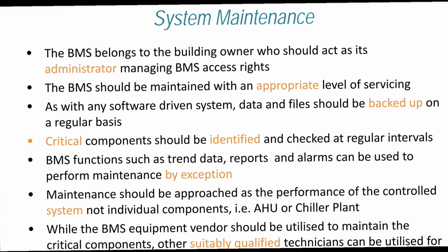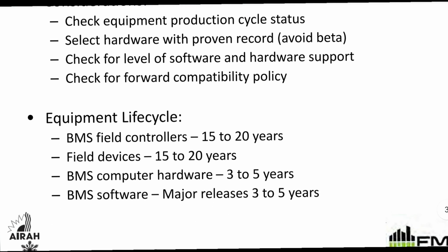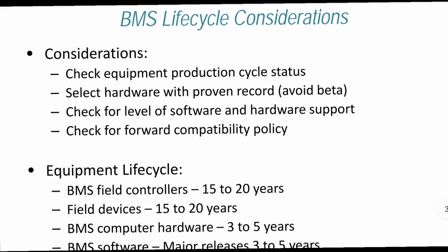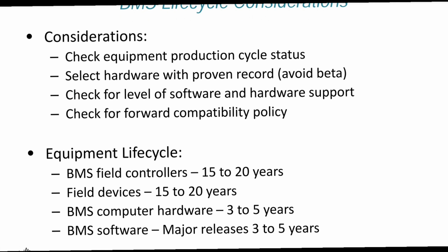approached as the performance of the control system, not individual components. Example: AHU and chiller plants. While the BMS equipment vendor should be utilized to maintain the critical components, other suitably qualified technicians can be utilized for the field equipment. Okay, this is the BMS life cycle consideration. Check equipment production cycle status. Select hardware with a proven record. Avoid beta. Check for level of software and hardware support. Check forward compatibility policy.